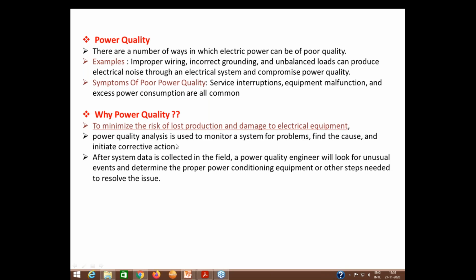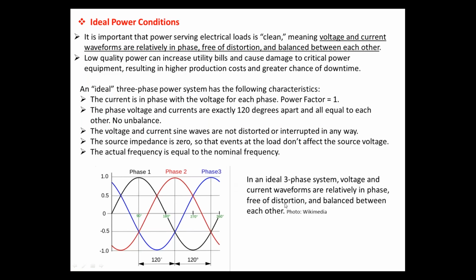Power quality checkup helps diagnose the problem beforehand, so you can correct it before your equipment fails. After system data is collected in the field, a power quality engineer will look for unusual events and determine the proper conditioning equipment. It's like a doctor suggesting that your sugar is on the boundary, and if you don't take corrective action, you may have a sugar problem. Likewise, this power quality engineer, generally an electrical engineer, will suggest conditioning equipment you need to install to avoid damage to your utility.